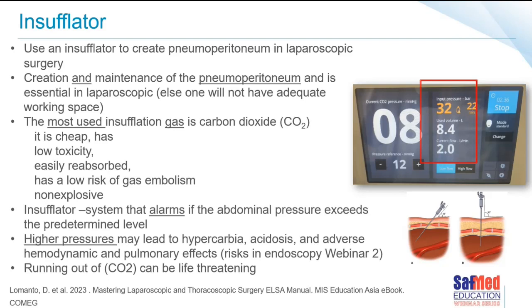The most used insufflation gas is carbon dioxide, CO2 as we know it. The reason for that is because it's cheap, it's got low toxicity, it's easily reabsorbed, and it has a low risk of gas embolism, and thankfully it's non-explosive. Of course, we want insufflator systems that can alarm if the abdominal pressure exceeds the predetermined level, because high pressures are very, very dangerous. They can lead to hypercarbia, acidosis, and terrible hemodynamic and pulmonary side effects. We'll carry on with more risks associated with high pressures and insufflation in webinar 2. Running out of CO2 can be life-threatening.